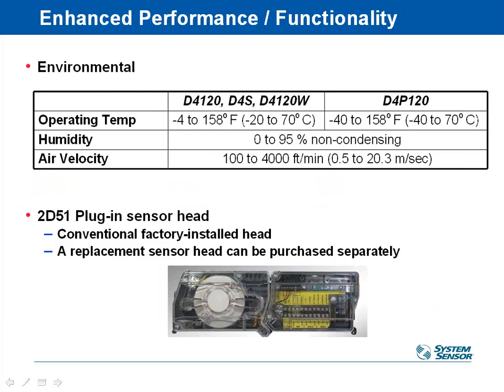Most of these detectors operate from -4 to 158 degrees Fahrenheit. There is a version that goes down to -40 if you have that application, but typically -4 is sufficient in our market. The other cool thing about System Sensor, other than some of these accessories and how easy it is to install the sampling tubes and the flexible rectangular or square design, is that it can handle low velocities, as low as 100 feet per minute. I believe it is the lowest velocity that any manufacturer can handle. So if you have an application with a rooftop or something like that, life is good. You don't have to worry about it. But if you have some specialty systems and you have low air velocity, this guy can handle that down to 100 feet per minute.